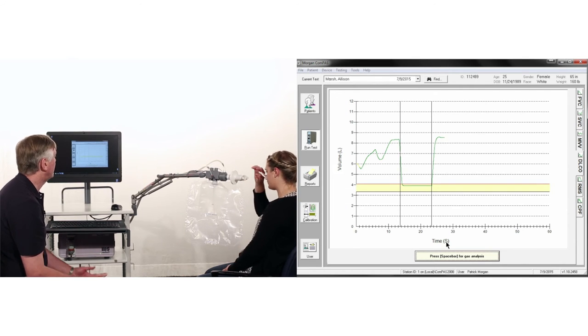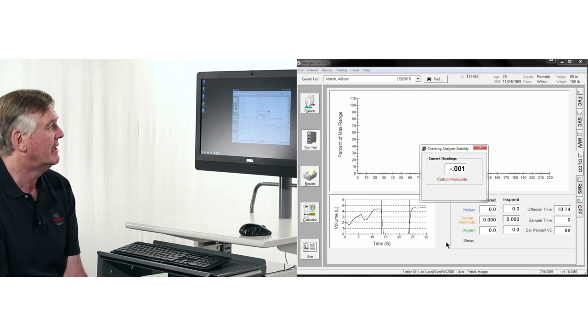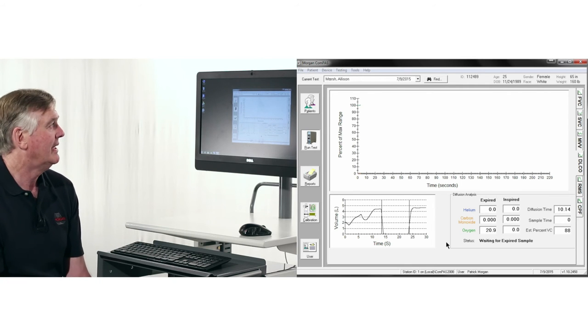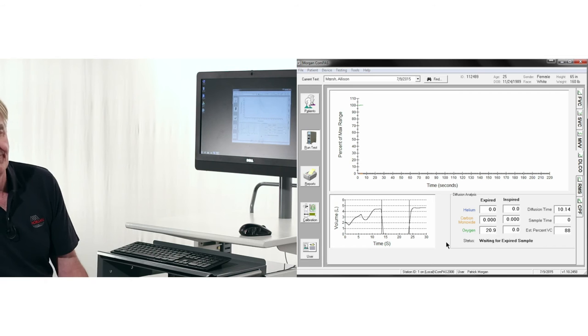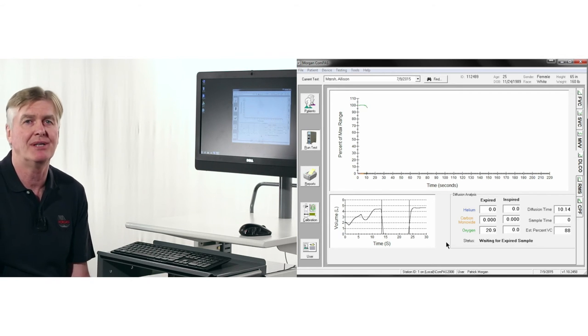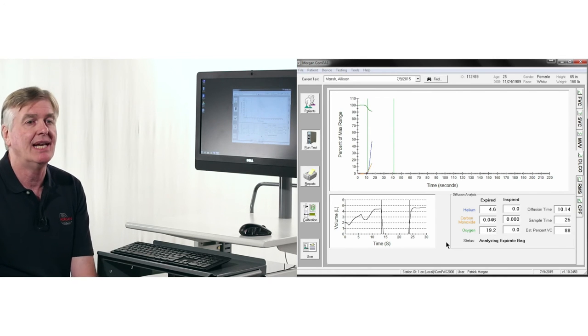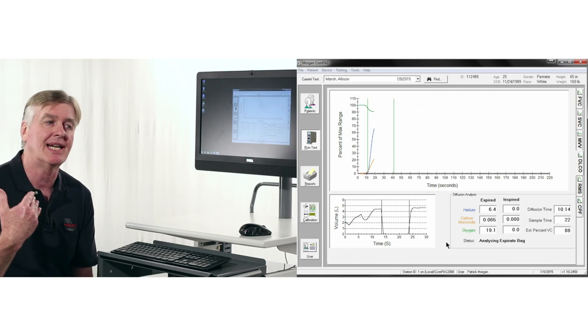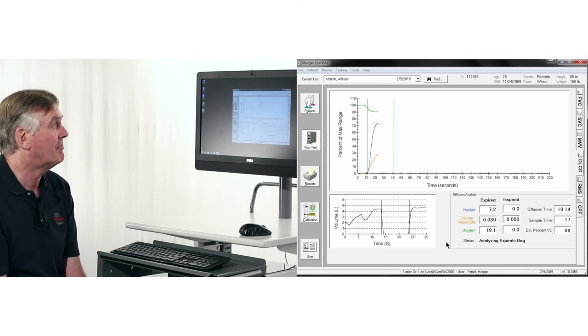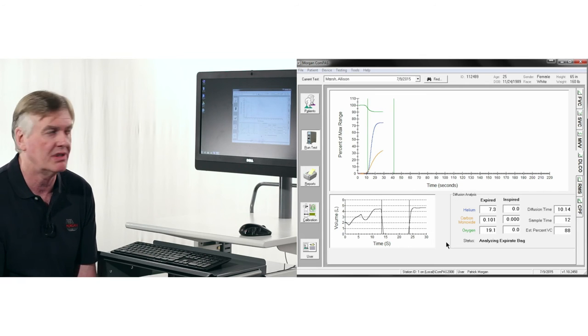The test is over for the subject, and we now gather the gas information. The timing of the gas measurement here is very deliberate. It's deliberately slowed down. This is counterintuitive to those companies that feel that everything should be rapid diffusion. Here, the diffusion is traditional measurement, and it's slowed down deliberately so that the gas that's in our subject's lungs can be cleared out. And when we repeat the test, we know we're getting a reliable second diffusion result.